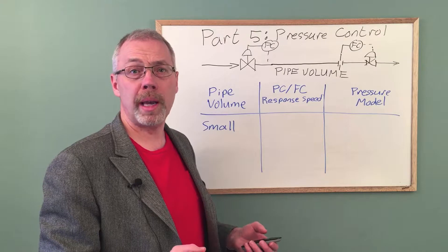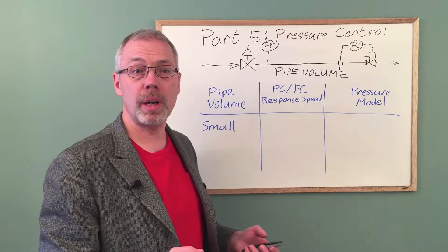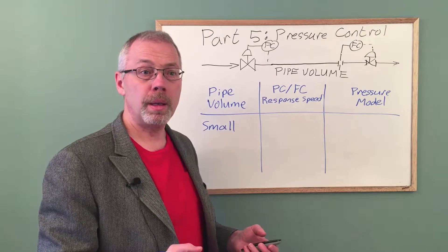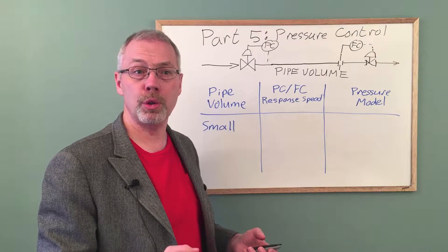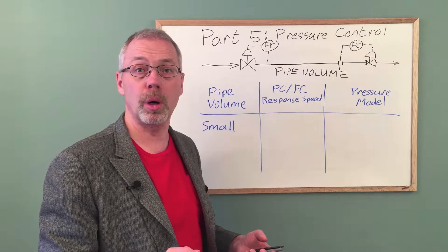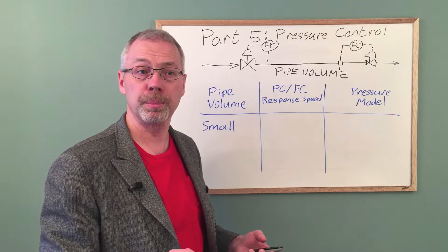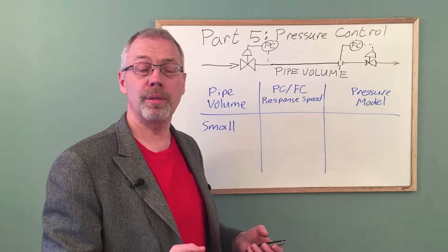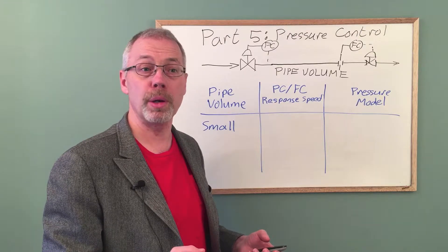In this case, fuel gas pressure is important because a steady pressure is necessary to maintain a steady flow rate. And we need steady pressure to ensure that high or low pressure alarms or trips are not encountered. Pressure must be tuned to respond fairly quickly and the flow controller will be tuned to respond somewhat slower.